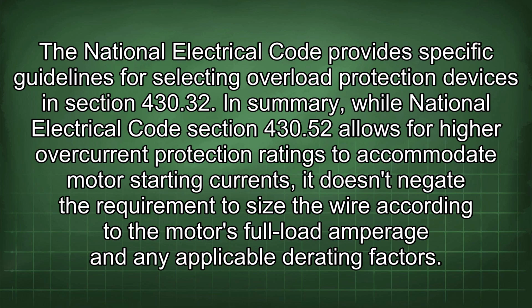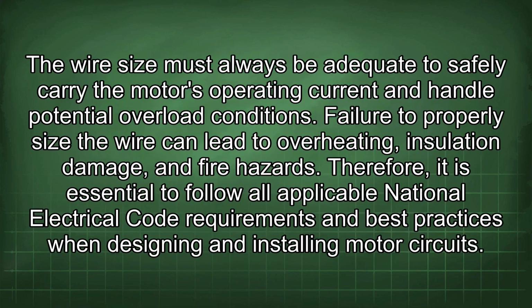wire according to the motor's full load amperage and any applicable derating factors. The wire size must always be adequate to safely carry the motor's operating current and handle potential overload conditions. Failure to properly size the wire can lead to overheating, insulation damage, and fire hazards.